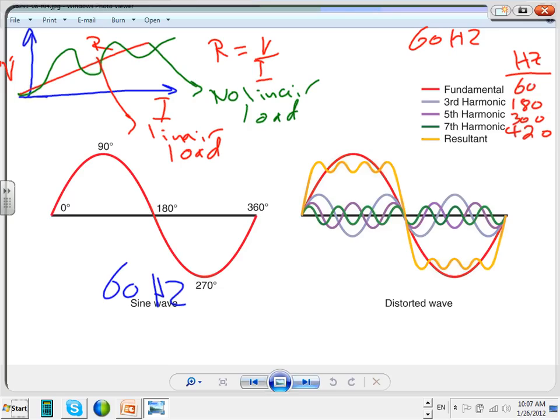If it's a third harmonic, this means I'm going to have 3 signals in 1 fundamental signal. Who cares? Yes, the frequencies are different. Look at the fifth. The fifth harmonic means in one 60 hertz signal, I want to look at how many signals. I have 5 signals on that color, the green 7 signals. We count the green signals, guys, from start 1, 2, all the way to 7 of them.